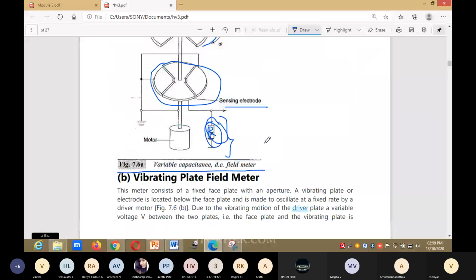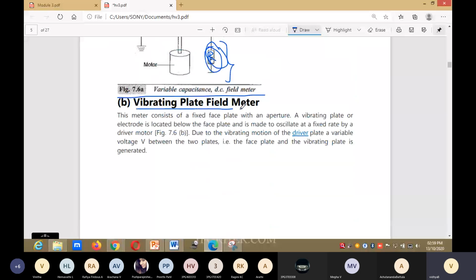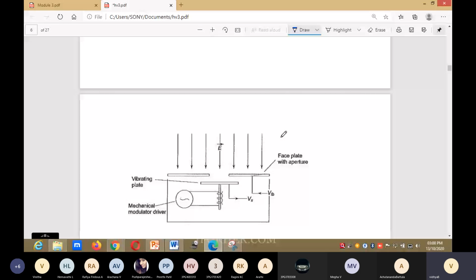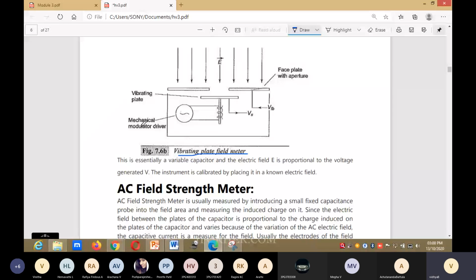Next is the vibrating plate field meter. This meter consists of a fixed faceplate with an aperture. A vibrating plate or electrode is located below the faceplate and is made to oscillate at a fixed rate by a driver motor. This is the diagram for the vibrating plate field meter, showing the vibrating plate and mechanical modulator driver, and the faceplate with aperture.